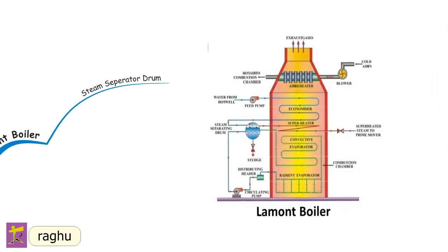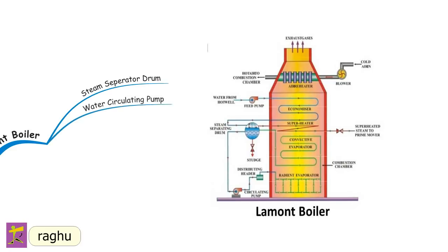The steam separator drum is placed outside the boiler assembly. It receives a mixture of steam and water from the evaporator tubes and feeds water from the economizer, where water particles present in the steam are separated. The centrifugal water circulating pump draws water from the drum through downcomers and circulates it by forced circulation at eight to ten times the weight of steam evaporated, which prevents overheating of the tubes.